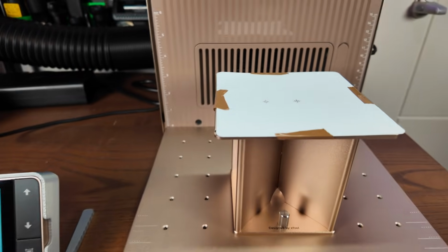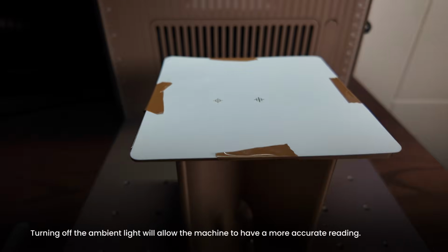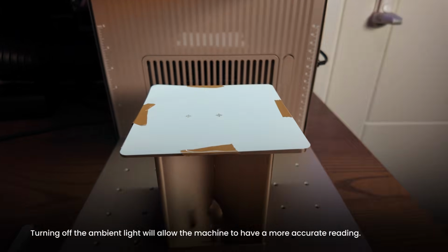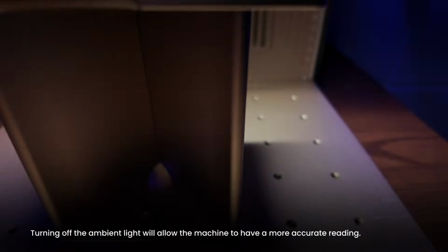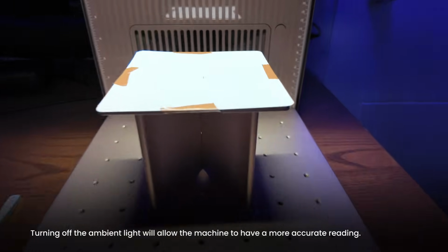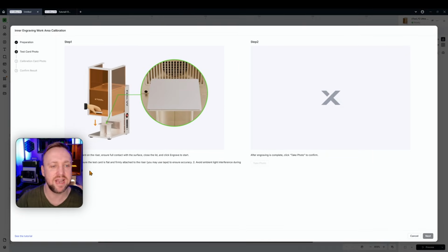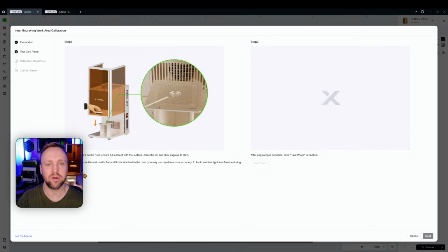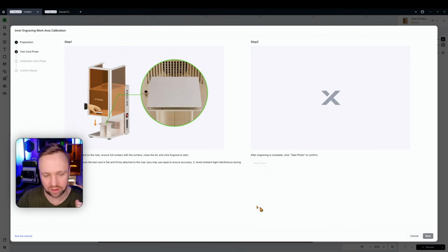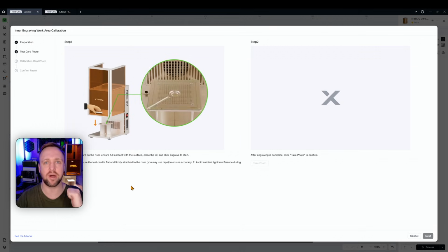The other thing it says is to avoid ambient light. So I am going to turn off all light around this room. I'm going to turn off the main light as well. And it's going to be darker, but this will allow it to have a more accurate reading. So I've turned off the ambient light. I have now taped it down, as you've seen. We're going to click the engrave button and it will then beep and assume it's ready to go. So what we'll do is go over and press our button. Now we're going to press the ready button.